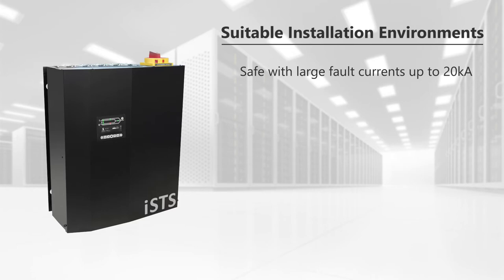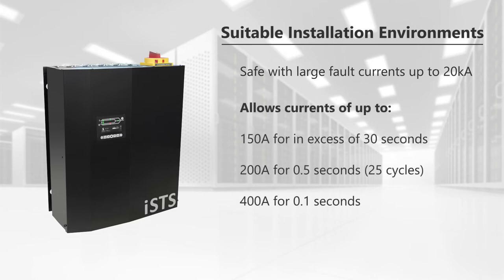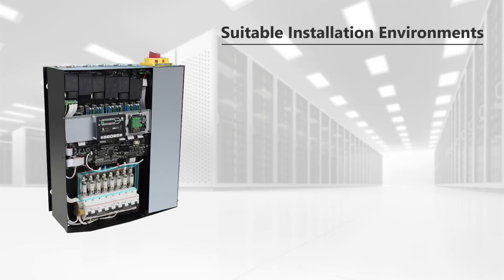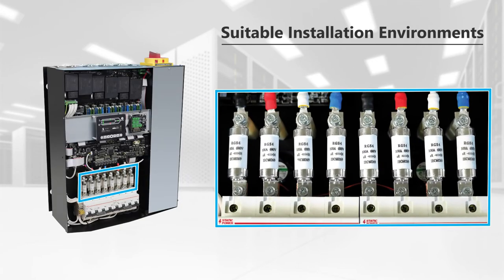The Model W is safe to install in environments with large fault currents of up to 20,000 amps. This STS allows currents of up to 150 amps for in excess of 30 seconds, 200 amps for half a second, and 400 amps for a tenth of a second. For safety and selectivity, fuses are incorporated.